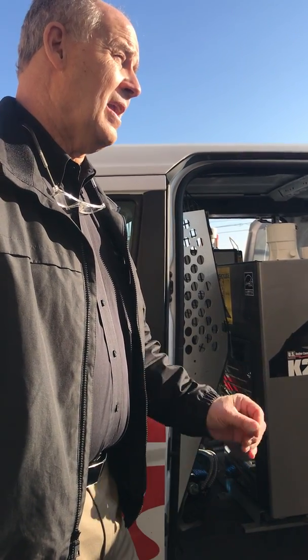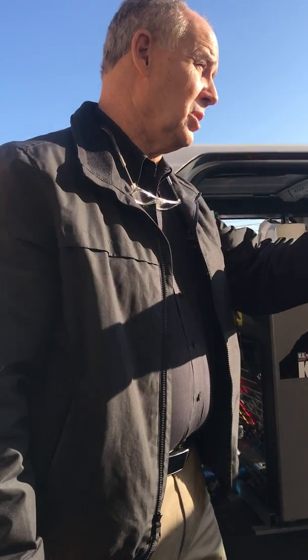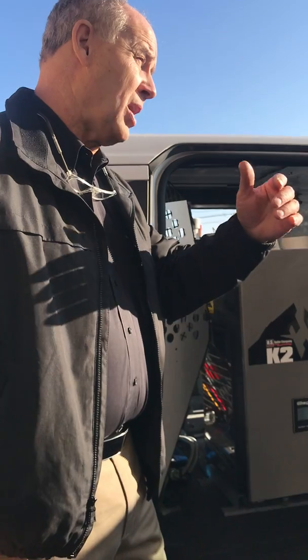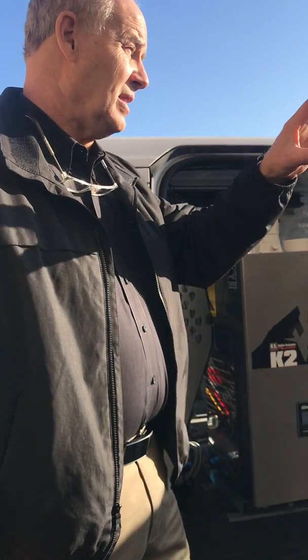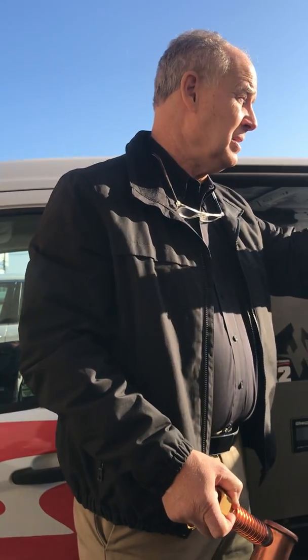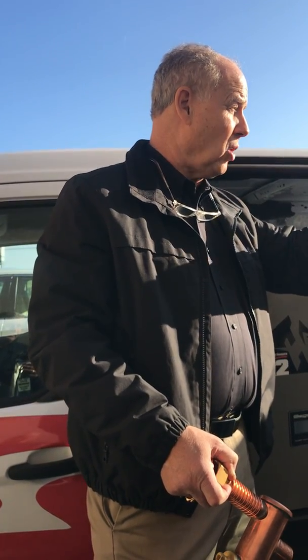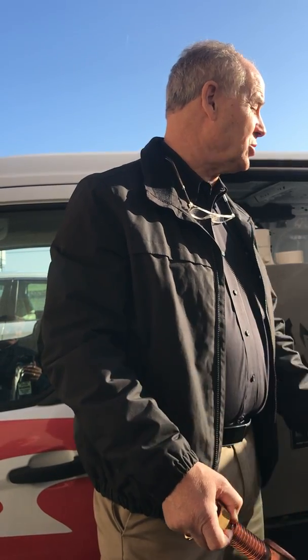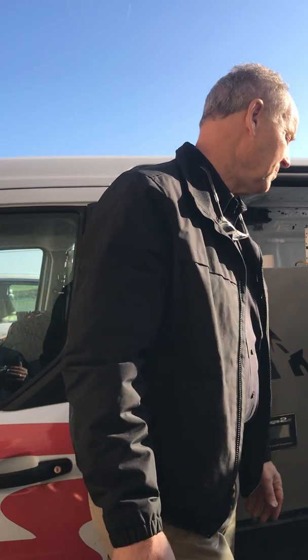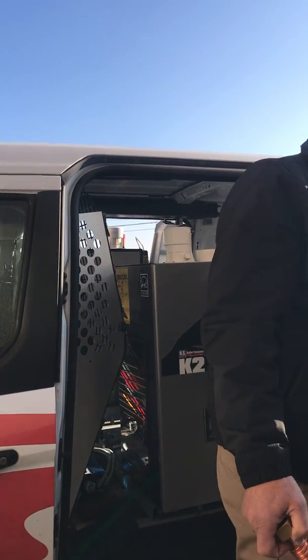It just runs. You should take the probe out and clean it once a year. And then the other thing is they have those cycle guards. So the new ones, they run for so many minutes and then shut it off. In case you have foam in your steam, foam on top of the water line, the bubbles all go down, and now it senses, because it conducts electricity across those bubbles. So the cycle guards actually lose some capacity for you too, because the boiler doesn't run for that whole hour. It shuts down. So you do lose a little bit, not that much, but just to let you know. So we'll go back up and we can do a little programming.